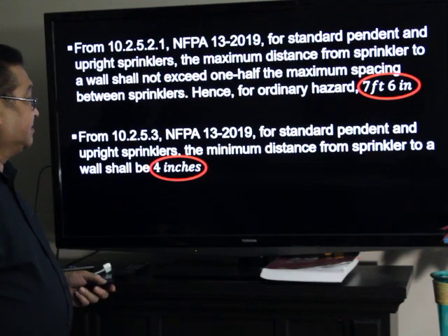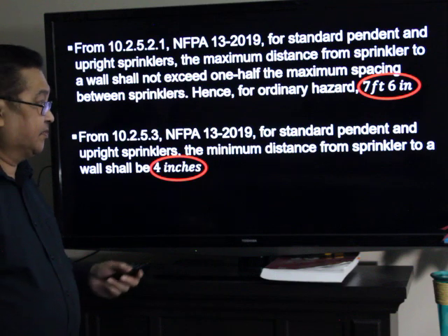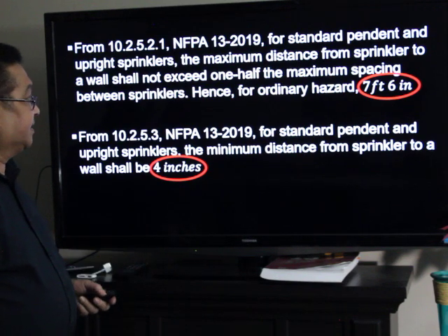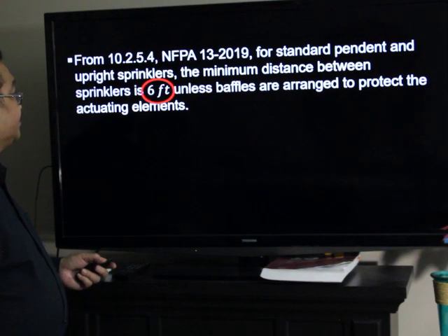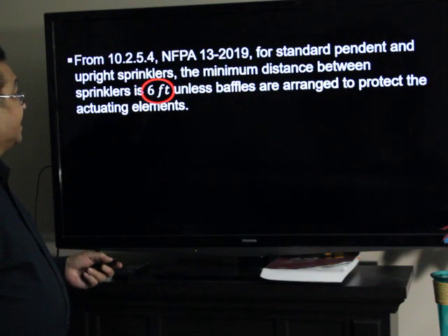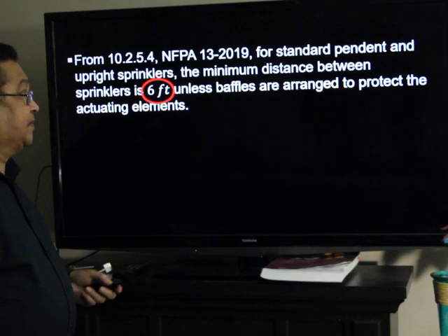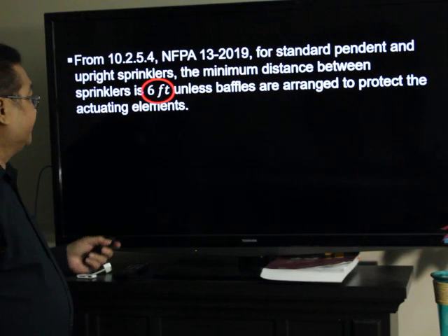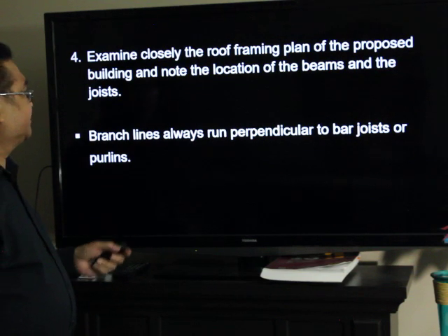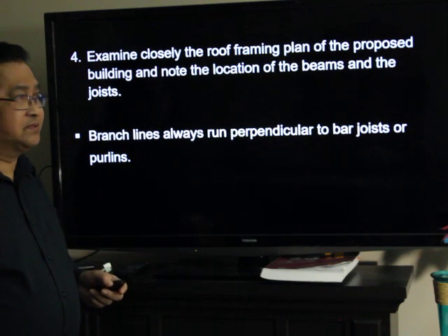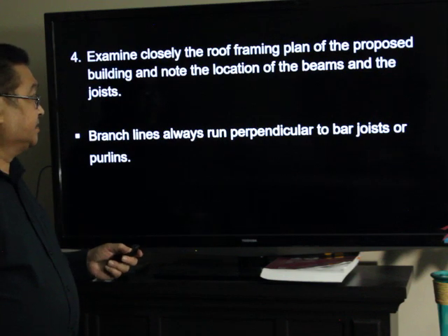And from the same standard, for standard pendant and upright sprinklers, the minimum distance between the sprinkler to a wall is 4 inches. And the minimum spacing between sprinklers for standard pendant and upright sprinklers is 6 feet, unless baffles will be provided to protect the actuating elements. Examine closely the roof framing plan of the proposed building expansion, and note the location of the beams and the joists. The branch lines will always run perpendicular to bar joists or purlins.